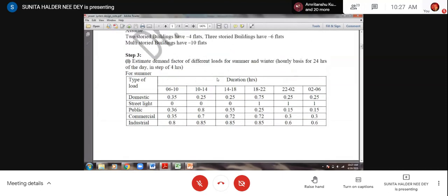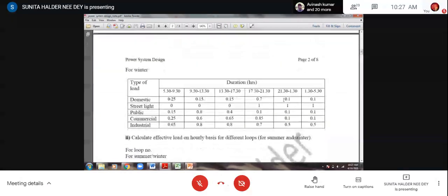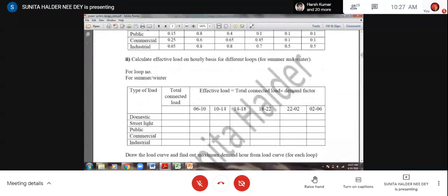Say maximum demand obviously occurs when there is maximum demand factor. So obviously from here you just calculate it right now and just fill up this table. That is, what is the effective load for summer or winter for your sub block. From step 3 onwards, all calculation will be on a sub block basis. So total connected load, what is the domestic load, street light load, all the information is now with you. You have a demand factor table, so from there you can calculate the effective load, or actually the maximum load in operation.